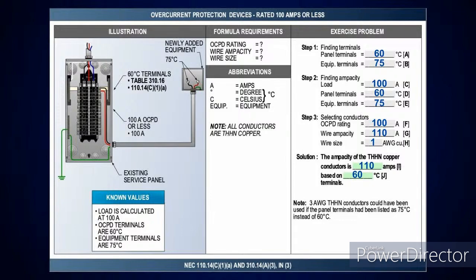So in step one, the panel terminals were 60 degrees C, the equipment was 75. We're telling you we have a calculated load here, we've already done it for you. That's 100 amps, okay? So we'll just follow this down. Then I look at my overcurrent device rating, go over to Table 240.6(A) for standard size. The next size up is going to be the exact same size, 100 amp. When I'm sizing the conductor, I'm going to base it on the 60 degree C column. When I pick that up in Table 310.16, the number one is good for 110 amps. So that THHN copper conductor is 110 amps, and that's based on which terminals? 60 degrees C.